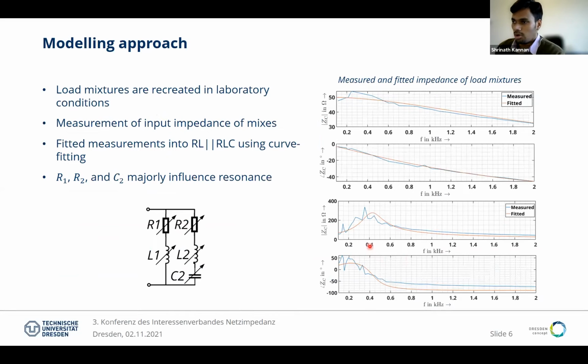The next step in the modeling approach is that the load mixtures are recreated in laboratory conditions at our institute in Dresden. These load mixtures' input impedances are measured with an invasive impedance measurement equipment. On the right, we have two exemplary cases showing the measured impedance curve and the fitted impedance curve using an RL parallel with RLC circuit.